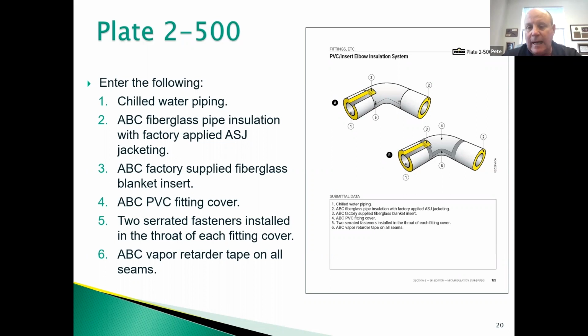Number 5, I'm going to list 2 serrated fasteners installed in the throat of each fitting cover. I could say number 5, detail A - 2 serrated fasteners installed in the throat of each fitting cover. It's very important that you list the number of fasteners you're going to put on each elbow, because the engineer is going to review this and approve it or not. If you have an engineer that likes 3 fasteners in the throat of the elbow, then you should list 3.